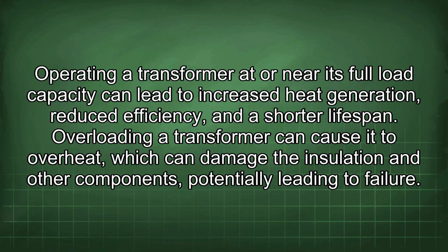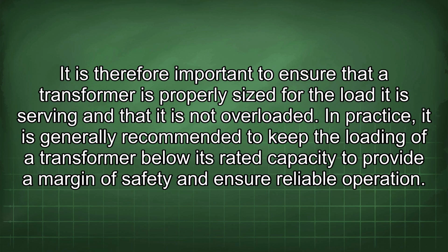Now, let's consider the implications of operating a transformer at full load or beyond its rated capacity. Operating a transformer at or near its full load capacity can lead to increased heat generation, reduced efficiency, and a shorter lifespan. Overloading a transformer can cause it to overheat, which can damage the insulation and other components, potentially leading to failure. It is therefore important to ensure that a transformer is properly sized for the load it is serving and that it is not overloaded.